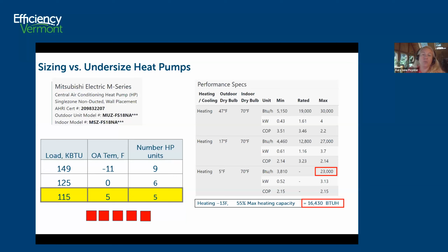Why would you undersize? Well, you can undersize only if you have an existing heating system. And if you're starting from new construction, that's a whole different story because you don't have a backup heating system. You probably are going to want to size for -11 or maybe somewhere between -11 and 0 because you're going to have to run straight electric heat.